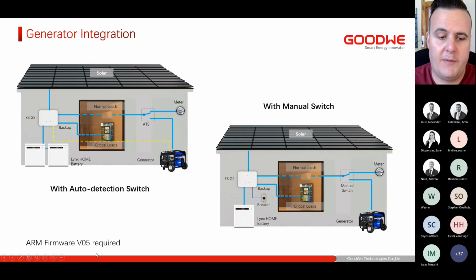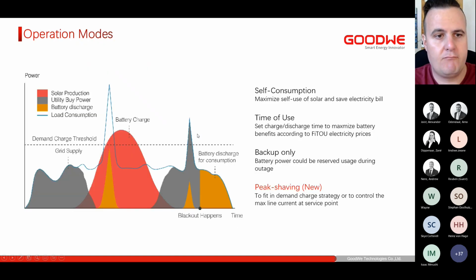Please note that this is all available from the ARM version 5, which we are releasing within this week. The next, the operation modes, as everyone knows, self-consumption, which is the default one, time of use, which you can adjust different charge and discharge times, especially if you are on a time of use tariff. Backup only to reserve the batteries to discharge only when the grid is unavailable. And then we also have peak shaving. Peak shaving is nice and more for larger utility customers. So this will be on our ET as well as on the ES. So that just gives us the flexibility to reduce those peak demands. So for business customers who are billed on kVA, that's a nice feature to have. But I think for homes, it doesn't really make a difference.